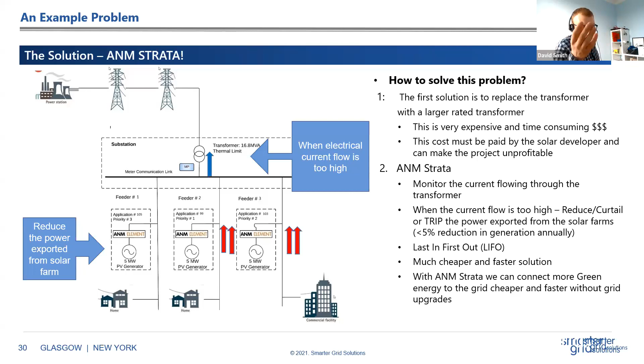So the other solution is to take some active control—this is a real example, which I've anonymized. We deployed our software, ANM Strata, which monitors the current flowing through that substation and transformer in real time. When the current gets too high, we curtail some of that generation, following a specific order, so we're only curtailing generation when it actually needs to be curtailed.